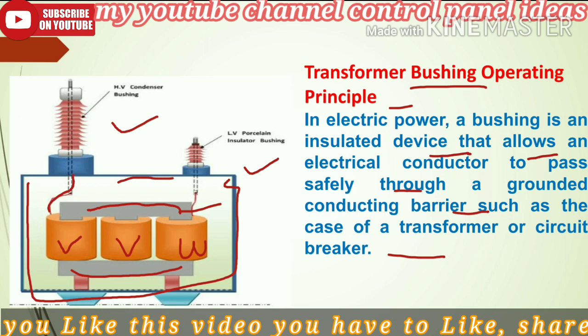So friends, the main purpose of bushings: this HV bushing connects the main terminal and the inside lead. This LV bushing is isolated from the full tank. Inside the space, there is oil.